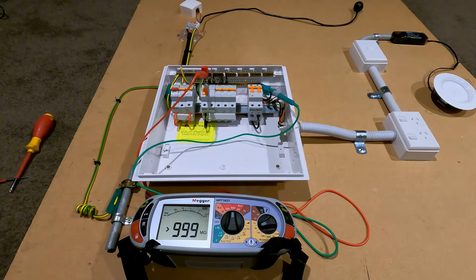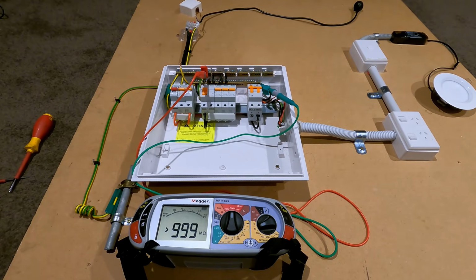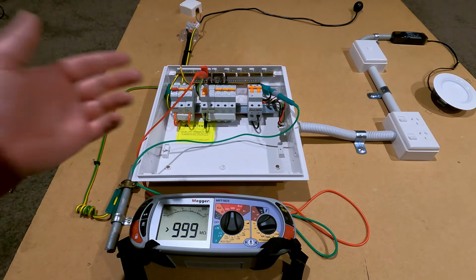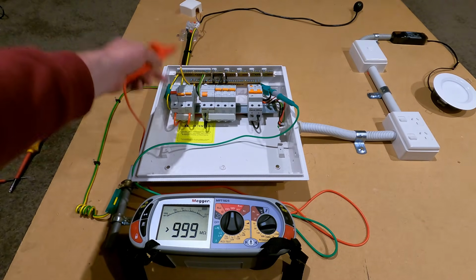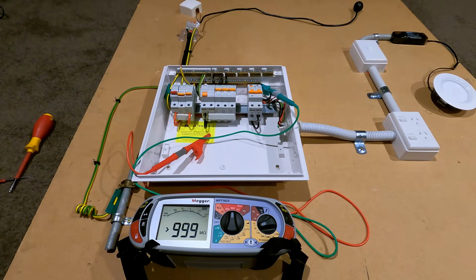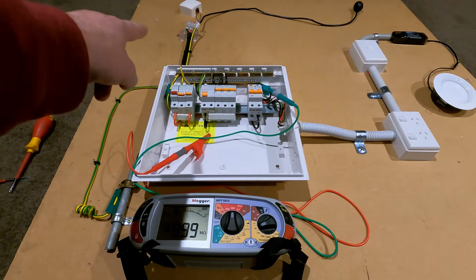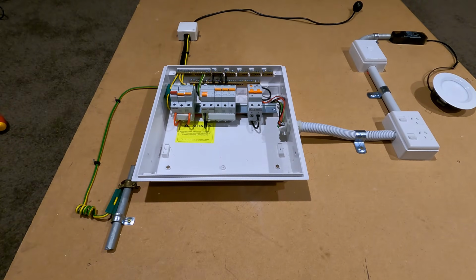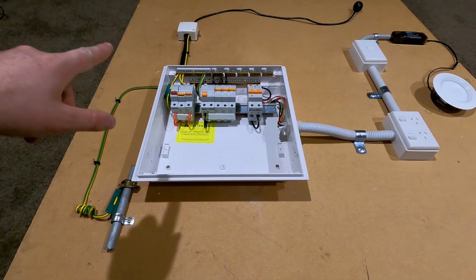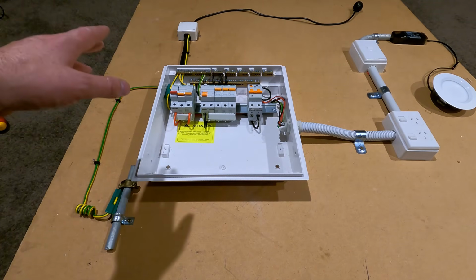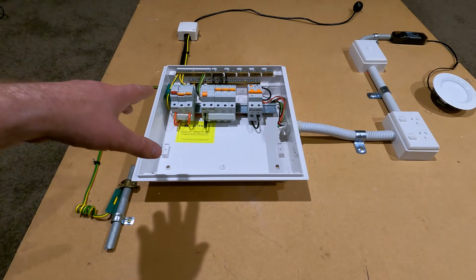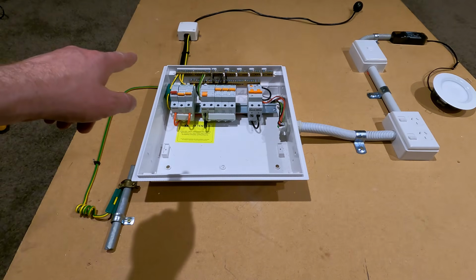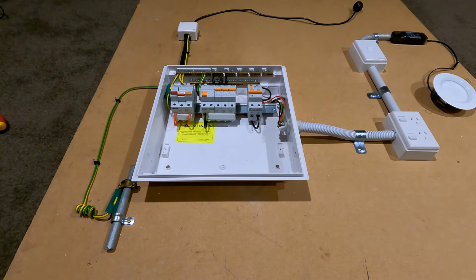Of course, the requirement is greater than 1 mega ohm. If you are getting near 1 mega ohm, I suspect there's something you've got to look at. And what I would be doing then is checking the load side of the RCDs, checking the mains separately, and just making sure we can find out exactly what's causing the low readings. But once you're happy with that, everything's good, we can now get rid of that link over there. When you are doing this insulation resistance test, just make sure that you go all the way back to the end of the line side to do the crossover, because if you're going to shortcut and do it at the switchboard, then you're not going to get your insulation resistance testing done on that mains cable, unless of course you're doing it separately.